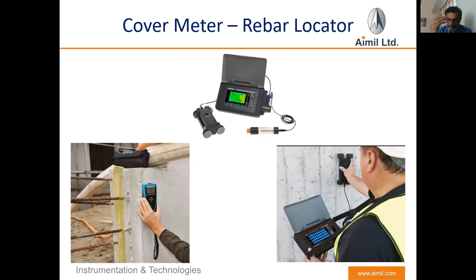This is how it is used. There is a probe to be put on the surface, and you will get the reinforcement steel location, and at that particular location, on that particular steel reinforcement bar, this instrument gives the concrete cover value. This is the probe which you move on the concrete surface, and as soon as you come near the reinforcement bar, it gives a beep sound. It also gives a light, through which you can understand that you are exactly on top of that reinforcement bar, at that location, and what the concrete cover is there.